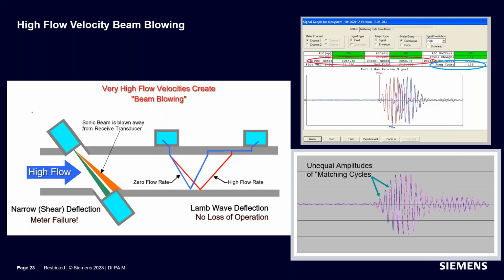between the up and downstream signals on the first wave of the received signal. Then we look at the differential on the fifth wave, which is the end of the transmit. When we transmit, we send out 5 pulses, and those 5 pulses account for this buildup in amplitude. Then we stop transmitting, and it falls off. So at the end of the transmit, we look at the same differential, and we calculate the effect of the beam blowing.